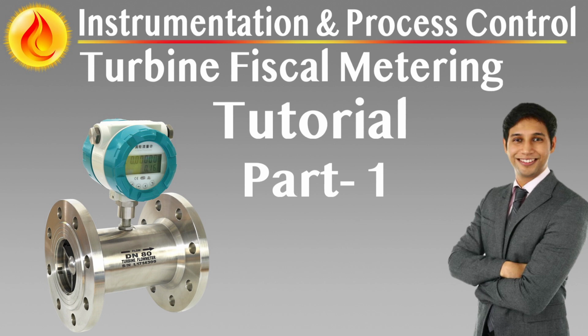Comprehensive uncertainty analysis. The manufacturer is responsible for submitting a full uncertainty analysis, quantifying the contribution of each metering component. This analysis must include statistical treatment, coverage factor k=2, sensitivity coefficients, environmental effects, and linearity deviations. The result must show that cumulative uncertainty lies within contractual thresholds. Without this analysis, system approval for fiscal use is incomplete.